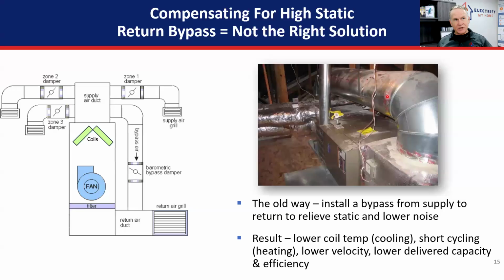In order to compensate for high static pressure, we've had some pretty crazy ideas over time. And one of them was a return air bypass. So you find systems out there that still have this. And yes, a bunch of them are uninsulated in the attic space. But what is the problem with putting one of these in?